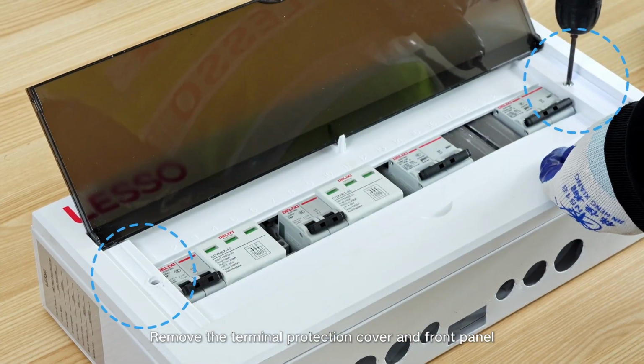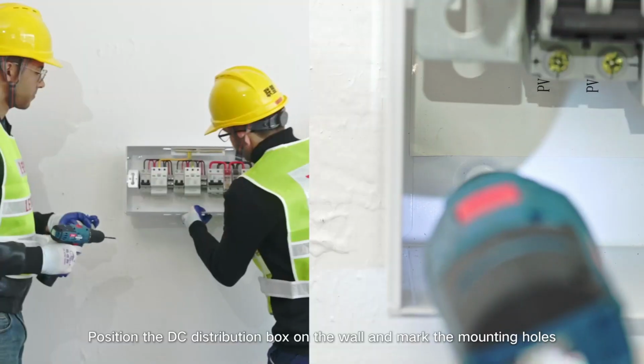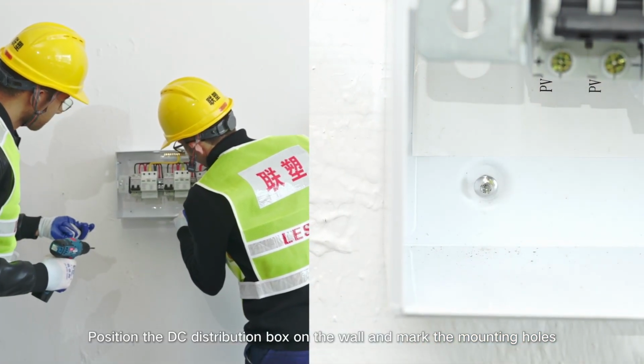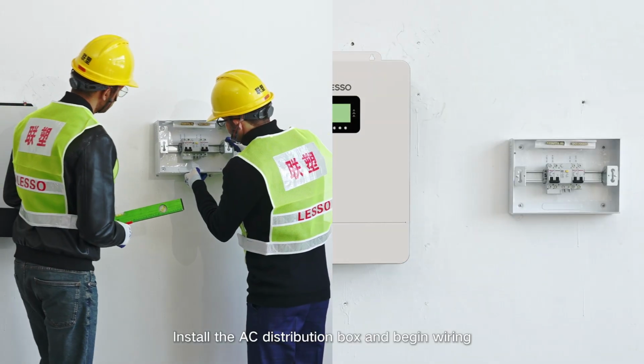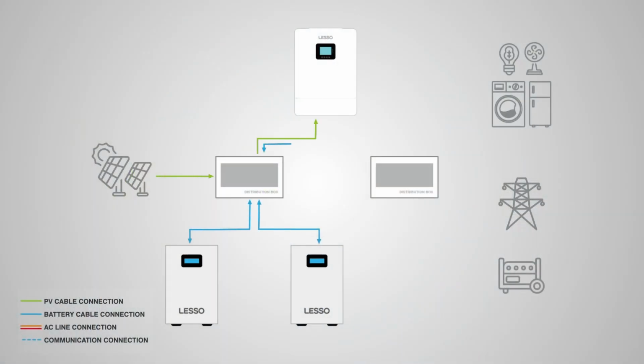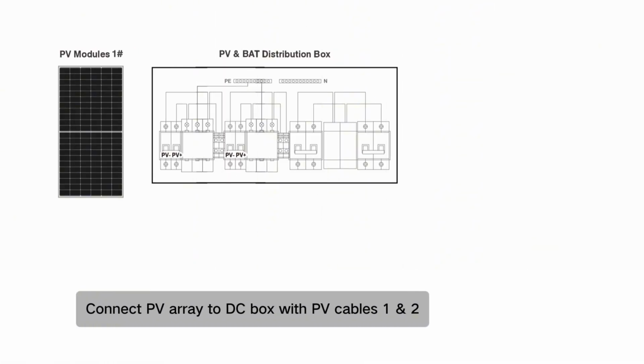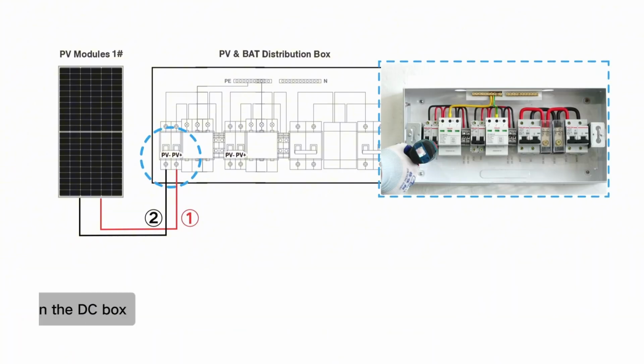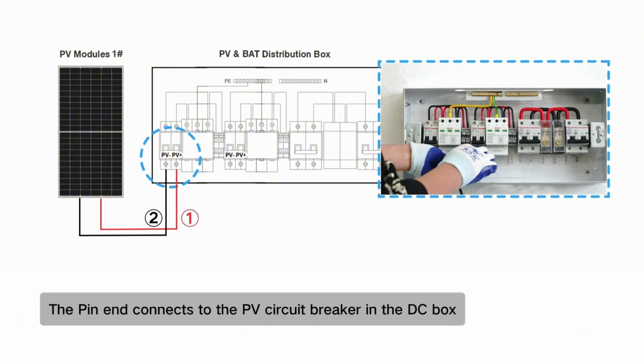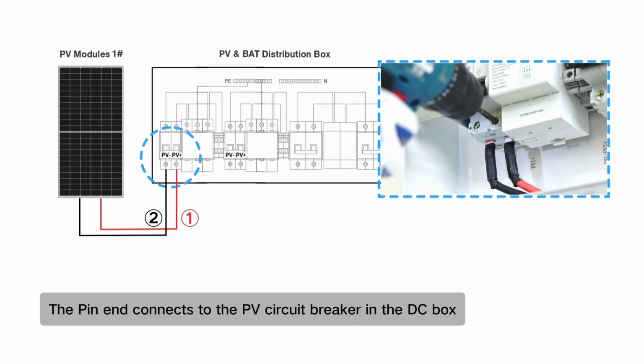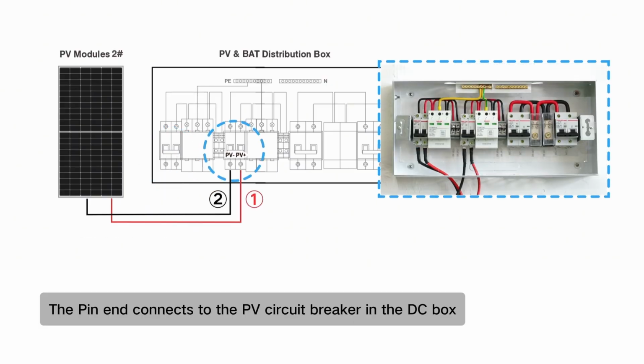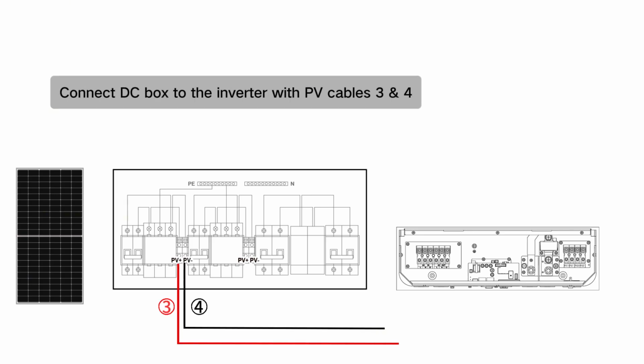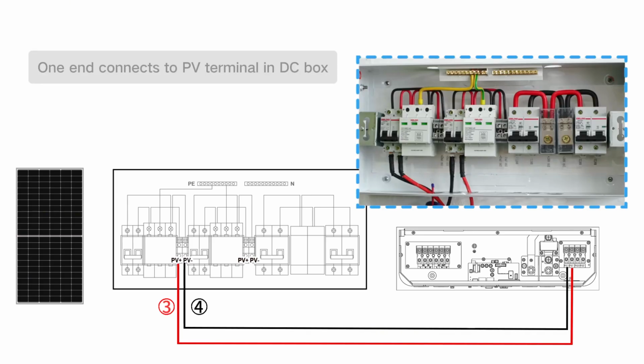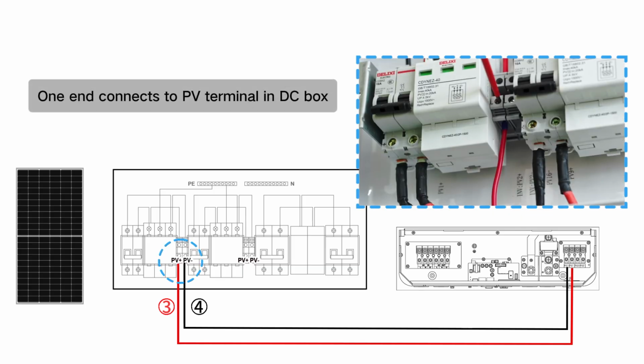Remove the terminal protection cover and front panel. Position the DC distribution box on the wall and mark the mounting holes. Install the AC distribution box and begin wiring. PV connection. Connect the PV array to the DC box with PV cables 1 and 2. The pin end connects to the PV circuit breaker in the DC box. Connect the DC box to the inverter with PV cables 3 and 4. One end connects to the PV terminal in the DC box.